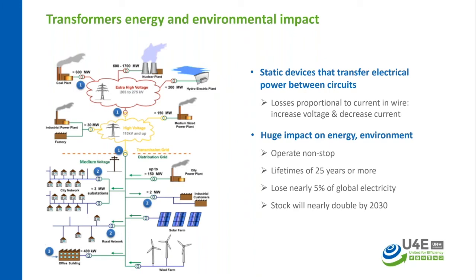So you can see the transformer, in spite of being a static device, is one of the efficient electrical products, because this product is in the chain from 400 kV up to sub-distribution level and distribution level. There are various voltage transformations happening, and cumulatively these transformers are adding losses to the tune of 5 to 6% as the technical losses.